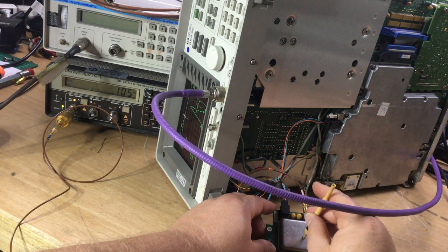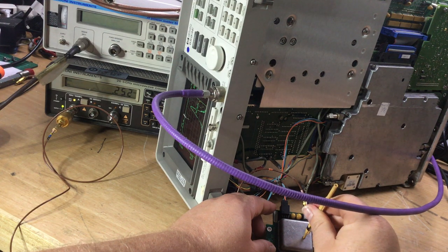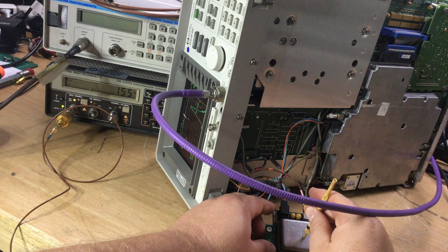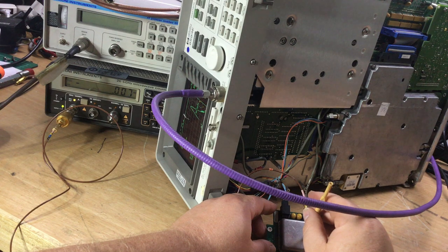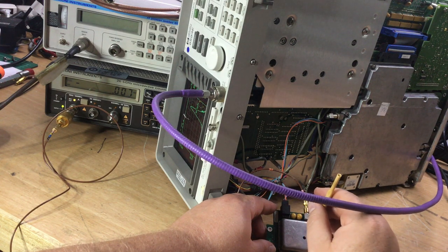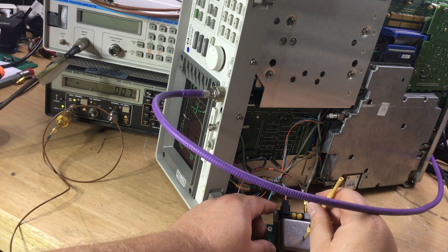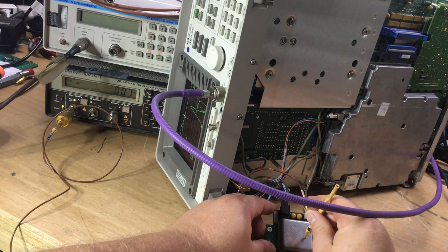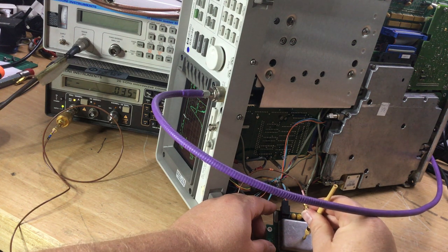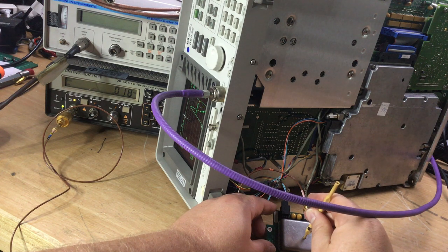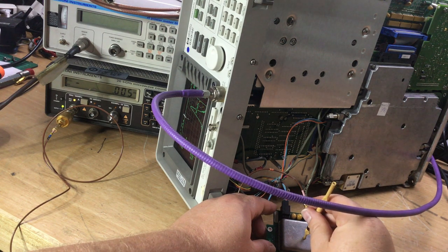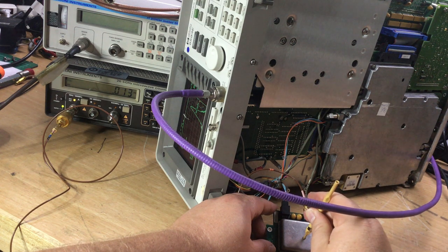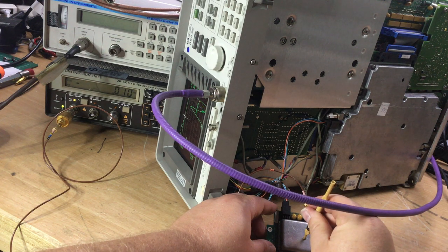Probably that 600 megahertz oscillator is just free running, and it's not in phase lock with the reference oscillator. And that's probably the problem now, because the fact that the reference oscillator is having no influence on the 600 megahertz frequency generation in the third converter means potentially the oscillator is just free running, and it's not actually phase locked. So that means, no matter what frequency the reference oscillator is adjusted to, as per the earlier experiments that we did, it merely implies that there is no relationship between the reference oscillator and the phase lock loop, PLL, which there should be, obviously. And that's what would ultimately bring the frequency of the instrument back into stability and accuracy.